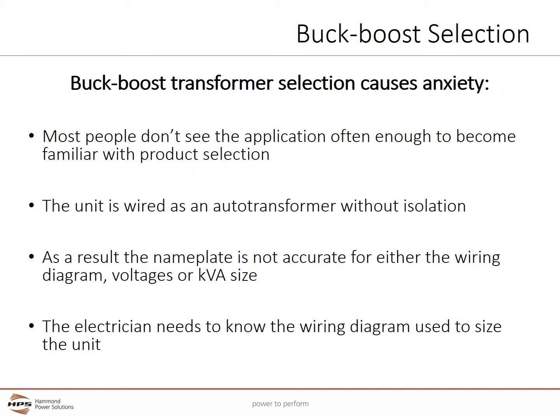Buck boost transformer selection has a tendency to cause anxiety for several reasons. Most people don't see the application often enough to become familiar with the product selection. The unit is wired as an auto transformer without isolation, which means the nameplate is not accurate for either the wiring diagram voltages or kVA size — and everyone is taught to review and obey the nameplate. Finally, the electrician needs to know the wiring diagram that was used to size the unit, and they need to wire the unit exactly as the buck boost wiring diagram states.